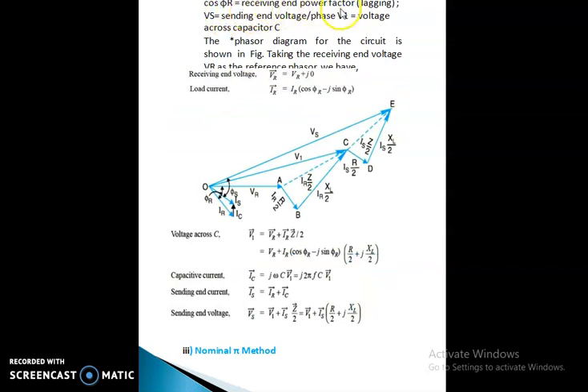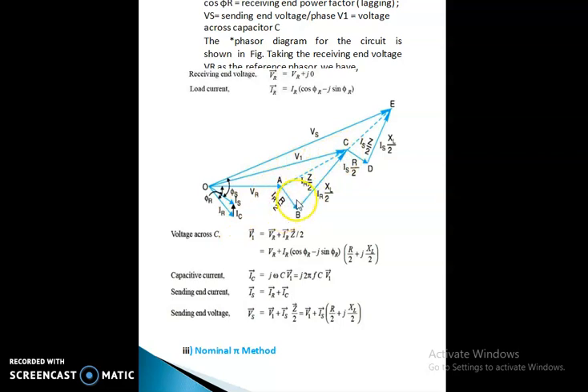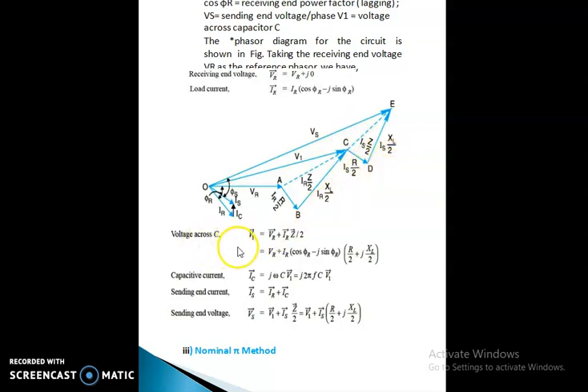The power factor is the receiving end power factor. Vs is equal to sending end voltage per phase. Taking the receiving end voltage Vr as reference voltage: Vr = Vr + j0. The load current Ir = Ir(cos φ - j sin φ). The voltage V1 is equal to Vr + Ir·Z/2, which equals Vr + Ir·(cos φ - j sin φ)·(R/2 + jXL/2).